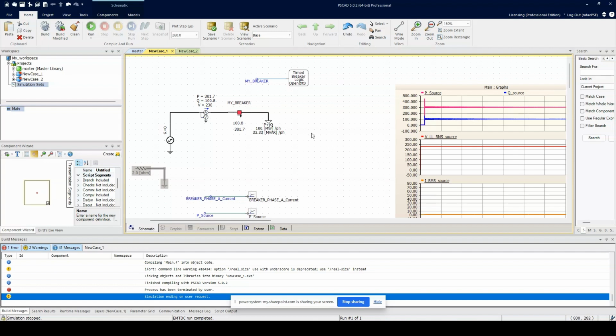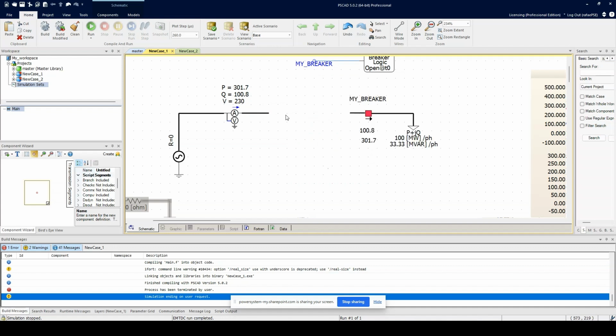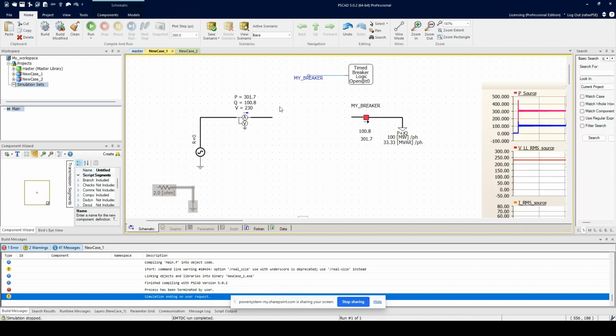So in this video, I want to take a little bit more time to explain what I mean by power flow of 300 here going into 100 megawatt per phase value, because this is a great place where we can look at this very important component in PSCAD, where we can break up the three phase, which is the solid line, into single phases. And why don't we just measure the flow just to prove ourselves that the per phase value or per phase flow is 100 indeed.